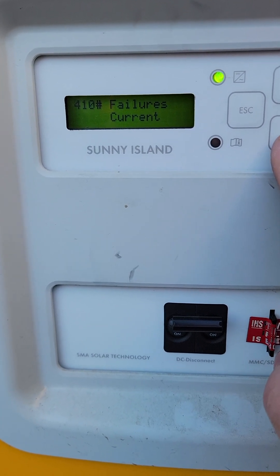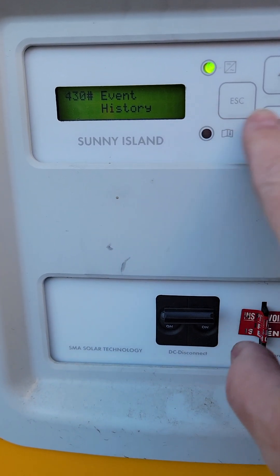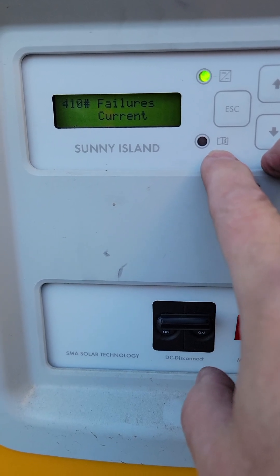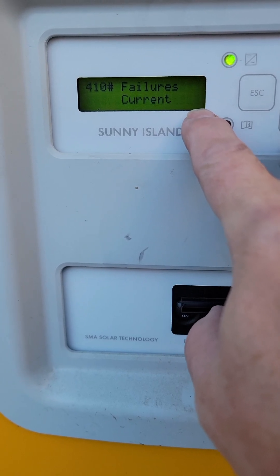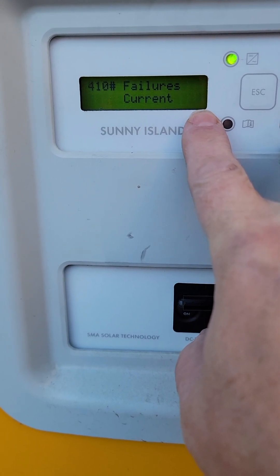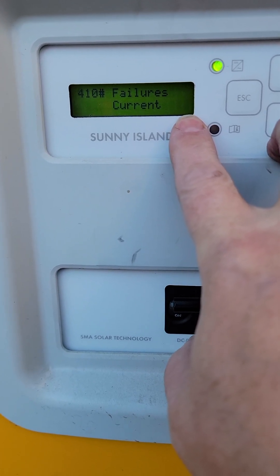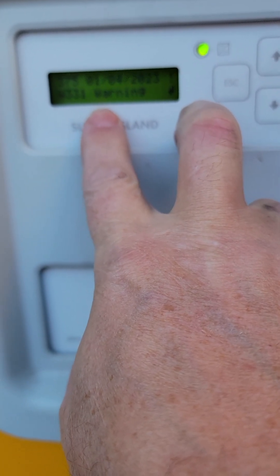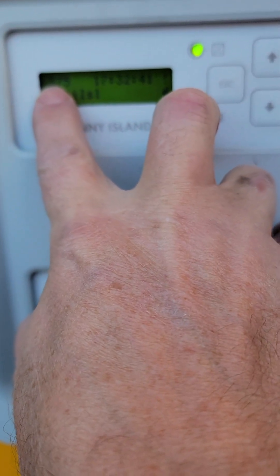There's the current failure or the history failure, and then there's the event history. We're going to go into the failures. Note that a warning or an event, even though there's a little flashing exclamation mark, might still allow the inverter to pull power from the generator or external power source. In this case, I'll go into current failures and you'll see that it's an anti-island warning — error number 331.